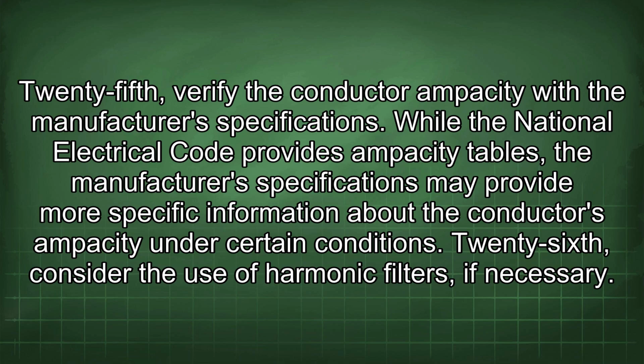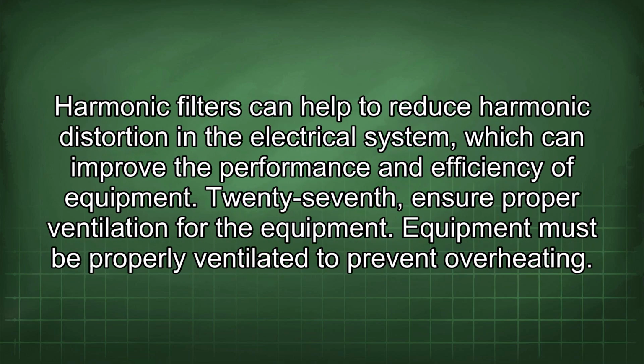under certain conditions. 26th, consider the use of harmonic filters, if necessary. Harmonic filters can help to reduce harmonic distortion in the electrical system, which can improve the performance and efficiency of equipment. 27th, ensure proper ventilation for the equipment. Equipment must be properly ventilated to prevent overheating.